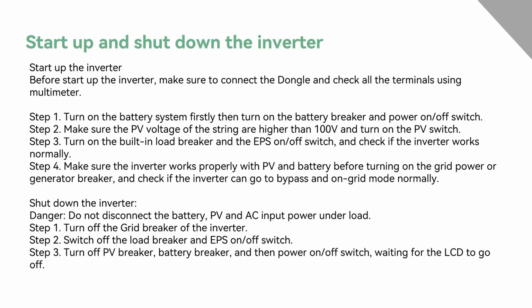Firstly, we need to use, for example, a multimeter to check that all the power inputs are within the right voltage range, for example the battery, grid, and the PV solar panels. And step one, turn on the battery system first, then turn on the battery breakers on the SNA 12K or any external battery breakers, and turn on the power on switch. After that, the inverter will start if the voltage of the battery is within the normal range, and the inverter will be powered on, and we can do some basic settings.